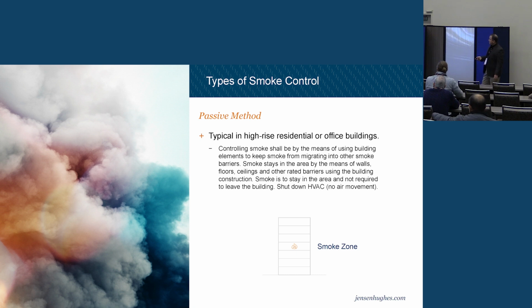All right, passive method. This one is probably pretty intuitive. The idea being, I don't do anything, but my doors are already closed. I've got smoke-proof enclosure doors in place. So if I have corridor doors, they're going to be maintained in the closed position. And then in a fire, hopefully that smoke stays contained, right? So I say hopefully. One of the biggest failure points to these is the little wooden triangles that you can jam under a door, right? Or IT. I can run IT through a wall. I don't need a precise hole. I need a hammer hole. So I just punch a big hole in a wall and run cable, right? So those are the biggest weaknesses to smoke control systems.